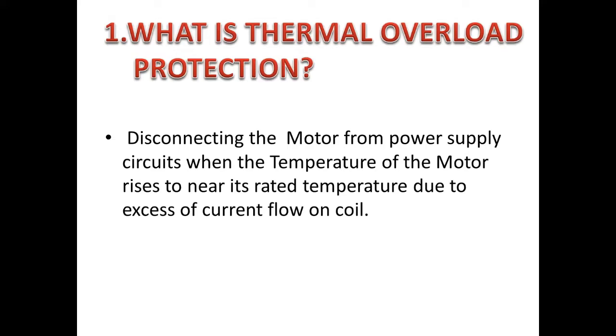First, we will see what is thermal overload. It is used to disconnect the motor from the power supply circuit when the temperature of the motor rises nearer to its rated temperature due to excess of current flow in the coil. When the motor is in running condition and reaches nearer to its rated temperature, it has to disconnect from the supply in order to avoid overheat. But if you have an RTD additional component in the motor, it will consider both the current flow in the coil and the environment temperature. If you don't have an RTD, the relay will only calculate the current flow in the coil.